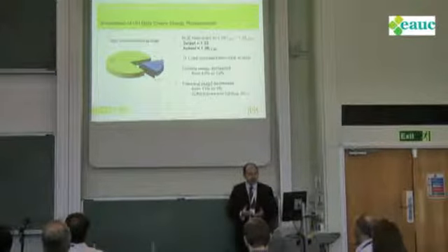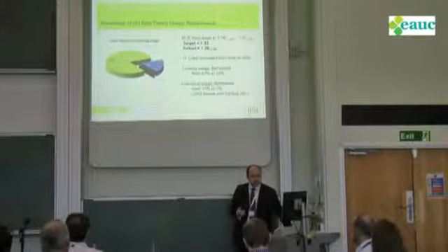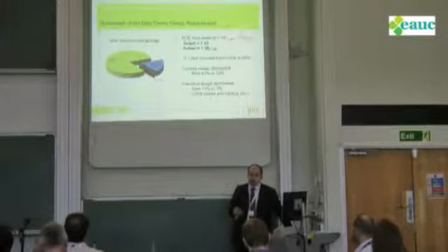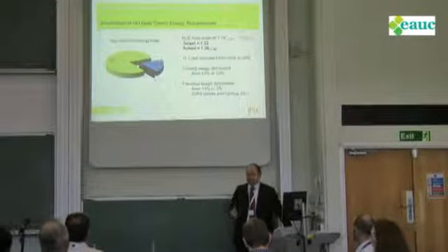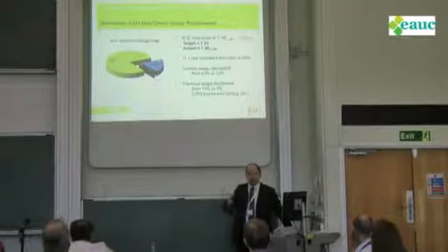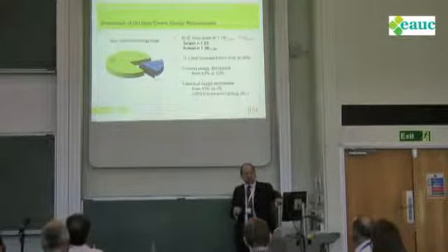Once we did the refurbishment, the IT load has increased to 80% of our total facility power usage, and our PUE is now down to 1.26, annualised across the year. It would be better, but we had quite a mild winter, so we didn't quite get as good efficiencies as we had hoped, because it is temperature dependent, obviously, throughout the year, which is why you have to annualise it. You can't just take it at one time. But it had gone down to 1.19 in the previous winter, where it was a lot colder.